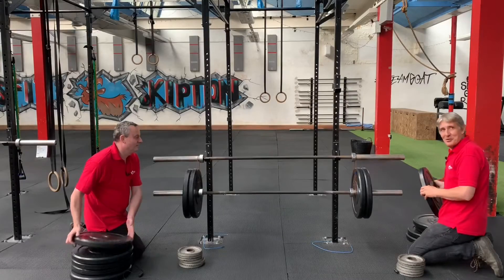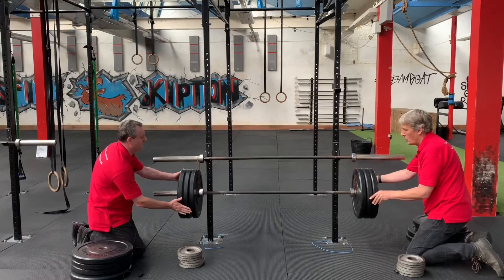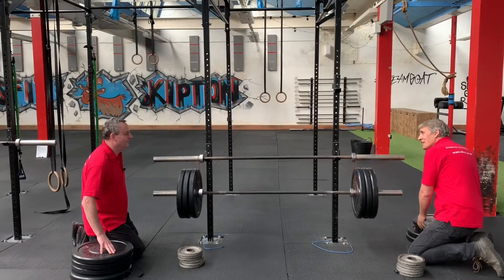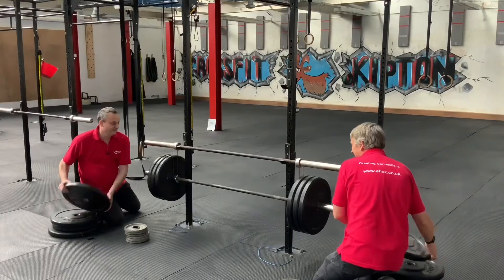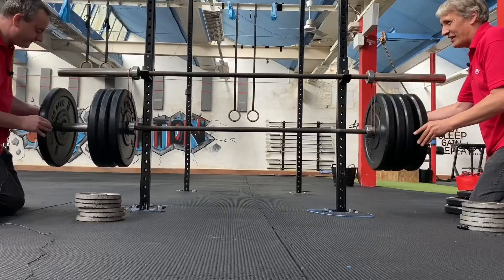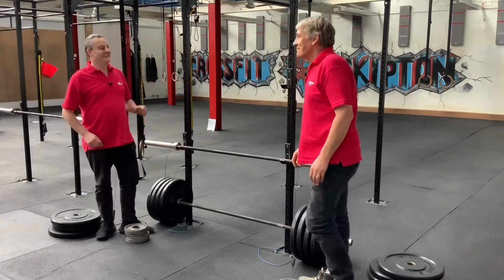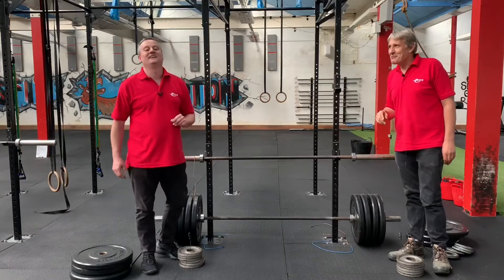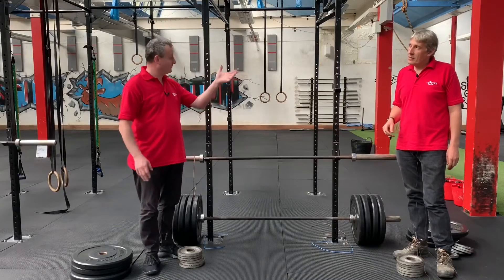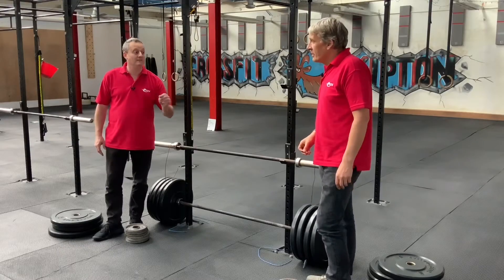Let's go in - okay it's fine. Piling it in here. What's that - that's 80 isn't it? Yeah, that's 80. So we're level pegging now. Go another 10. Okay, you nervous? I'm going to lose again - getting fed up of this. Oh, take it easy, take it easy! Win for Gaz? No - I think it's more of a dead heat Gary. Possibly I was slightly ahead. At 80 kilograms we've proved the point that the through crimp is actually a really good crimp connection.